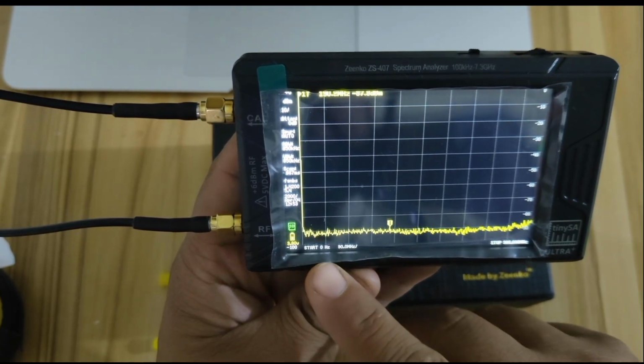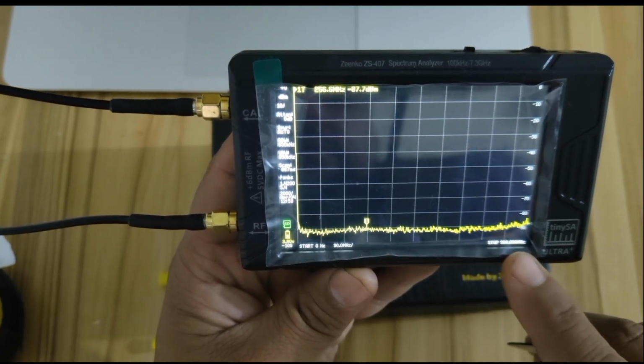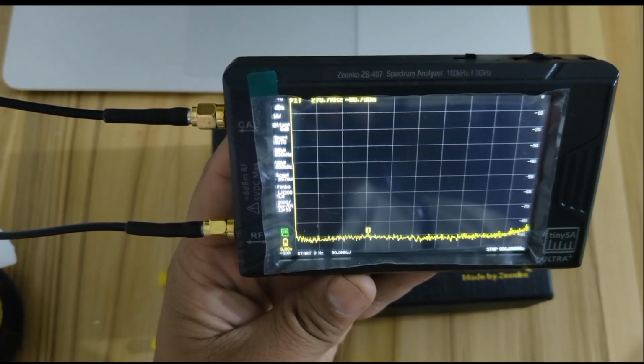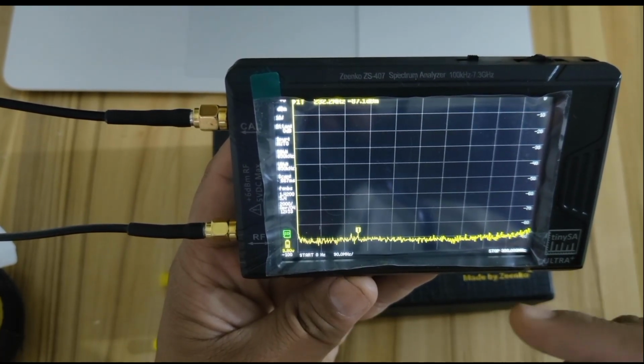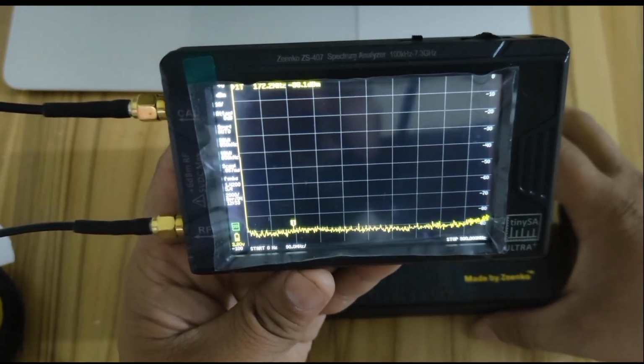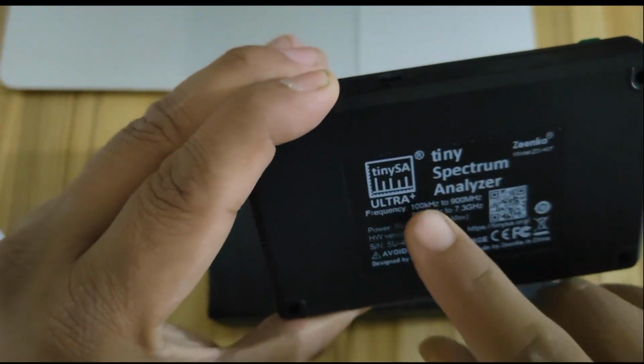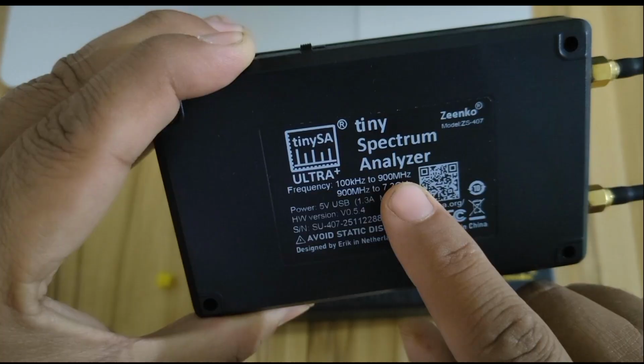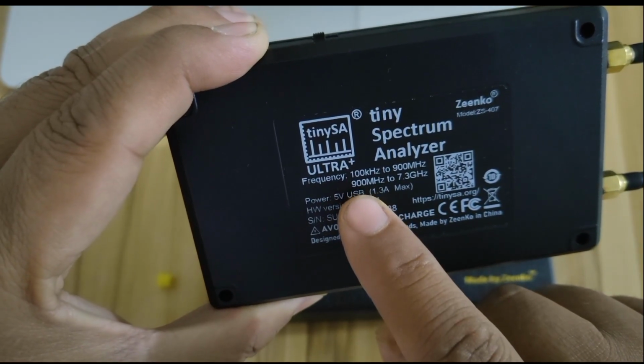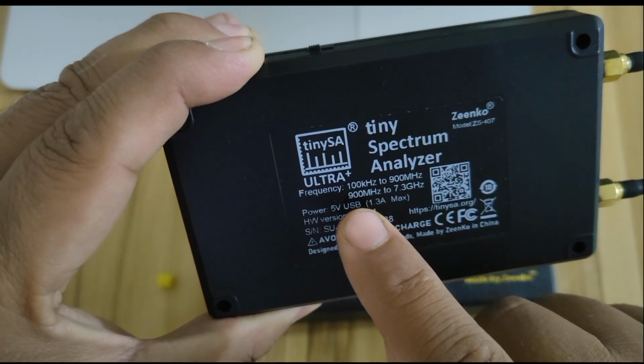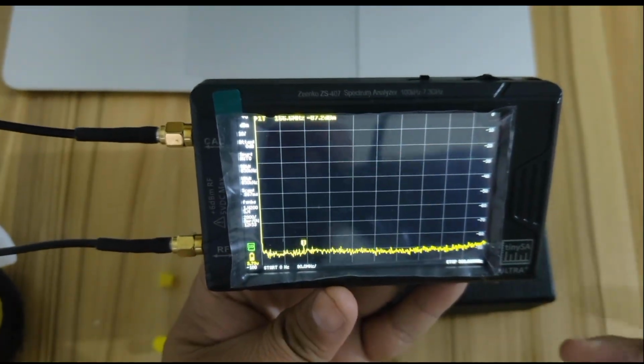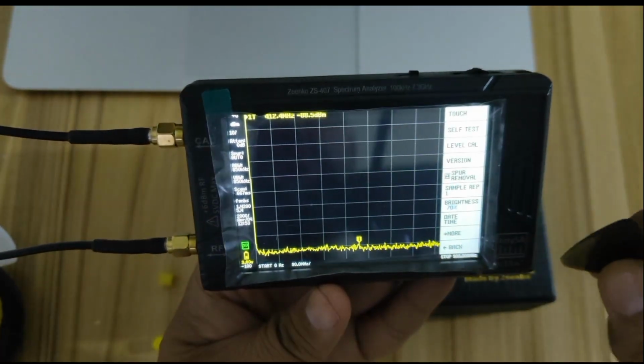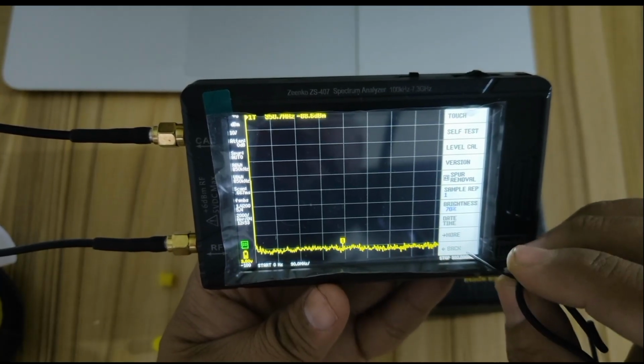Now, what you would see is a spectrum that is going from 0 to 900 megahertz. In order for you to actually look at the mode beyond 900 megahertz, because if you read it from the back of it, it says it goes from 100 kilohertz all the way up to 900 megahertz. If you want to use the ultra mode, which is actually going from 900 megahertz all the way up to 7.3 gigahertz, you need to actually enable your ultra mode.